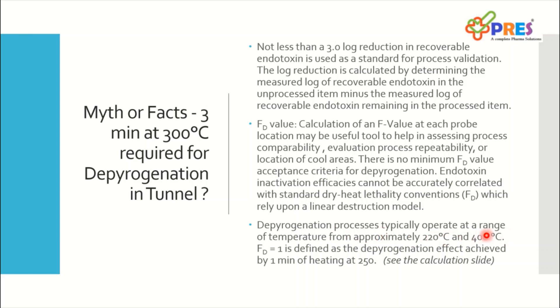The depyrogenation process typically operates over a temperature range of approximately 220°C to 400°C. FD1 is defined as the depyrogenation effect achieved by a minimum of 1 minute at 250°C. So when your process runs at 250°C for 1 minute, you get FD equal to 1. If we make an equivalency with moist heat: in moist heat, if your process is exposed for 1 minute at 121°C, your F0 value will be 1. For depyrogenation, we use 250°C as the reference temperature and FD instead of F0. We will see in the upcoming slides how changing temperature and time affects the FD value.